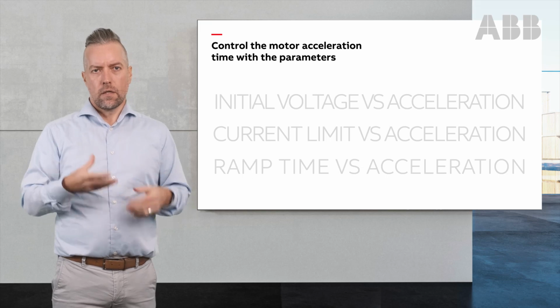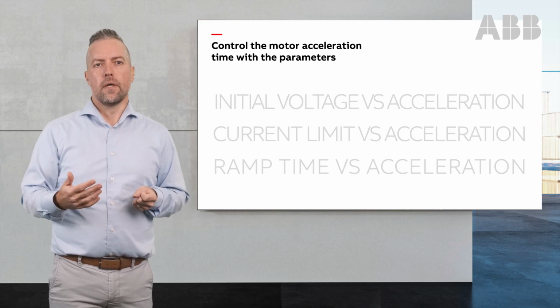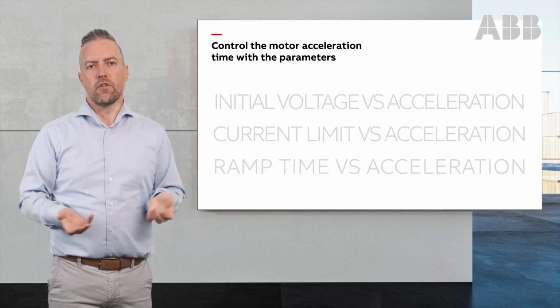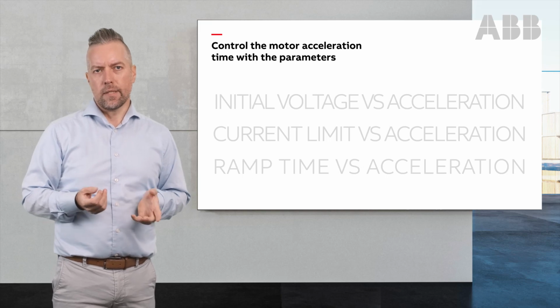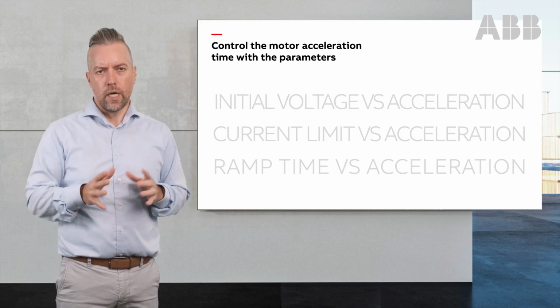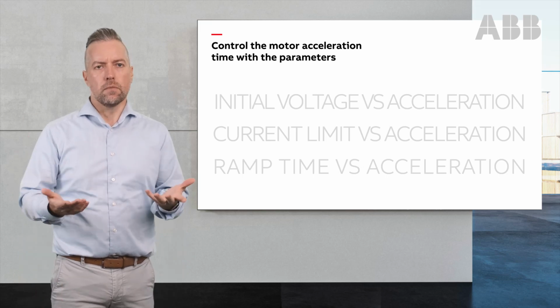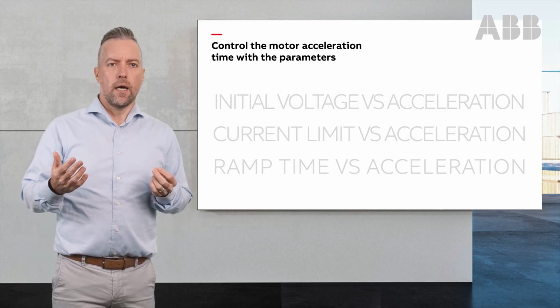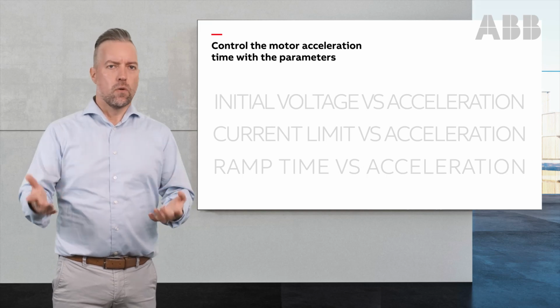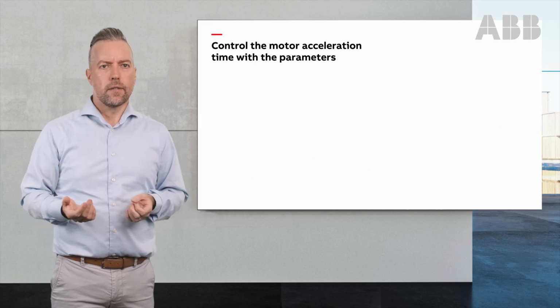But a good starting time of a motor is between 5 to 10 seconds. There is a really good window to get the application up and running as quickly as possible, but still minimize the torque and the inrush current as much as possible.